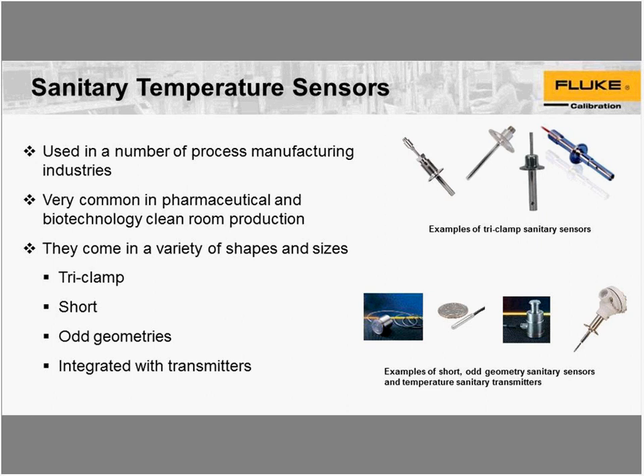As I've already said, these sensors are very common in a lot of manufacturing environments, in pharmaceutical, biotech, and food. Sanitary temperature sensors come in a variety of shapes and sizes. As the name suggests, they are designed to maintain cleanliness, so they are typically made out of a material that can be easily kept clean and is inert to the chemicals they're exposed to. Oftentimes it's stainless steel. The category we will mainly talk about today is the tri-clamp category. We'll talk a little more about what that is, but there are other sanitary sensors that may not have the tri-clamp flange on them.